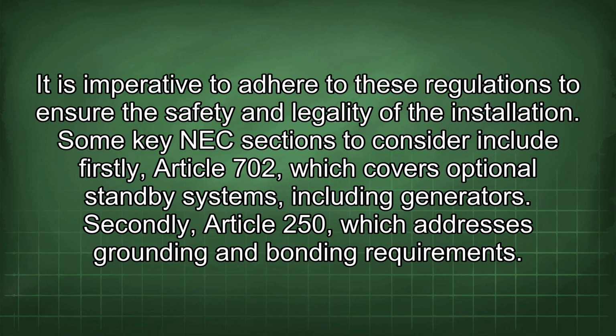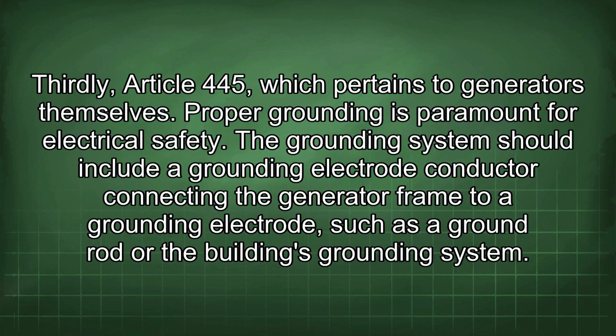Some key NEC sections to consider include: firstly, Article 702, which covers optional standby systems, including generators. Secondly, Article 250, which addresses grounding and bonding requirements. Thirdly, Article 445, which pertains to generators themselves. Proper grounding is paramount for electrical safety. The grounding system should include a grounding electrode conductor connecting the generator frame to a grounding electrode, such as a ground rod or the building's grounding system.